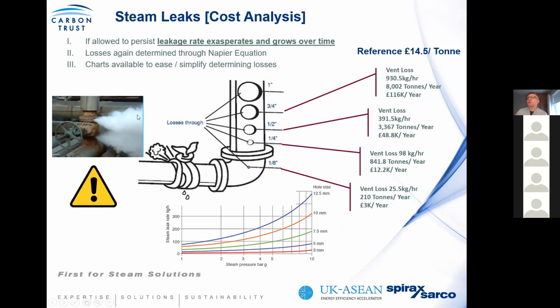Because often we recognize the leak is there, and the customer says, yes, we know it's there, but we need downtime to fix it. But simple things like understanding potential leaks help. As the leaks get worse, which is visible by the size of the plume, even a 1/2 inch hole could lose up to about 400 kg an hour, which is nearly 48,000 pounds, considered on a UK price of about 2.5 pence per kilowatt hour for gas, for example. So you should use the size of the plume as justification for senior management that you need the time required to make those repairs, because of the financial and energy impact.